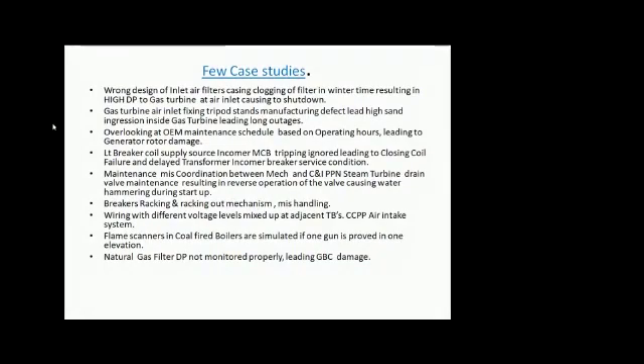The other thing is again a design issue, so proper engineering, because there is a quality matter. This is the second point. If you see gas turbine inlet filter tripod stands, I have seen that these tripod stands were supplied by a very famous, reputed manufacturer, but their sub-vendors, because they also do a lot of outsourcing. Even the biggest manufacturers don't manufacture everything in their own plant. They do a lot of outsourcing. When they outsource, the quality has to be seen properly. If they miss the proper quality, that will affect their own main equipment.